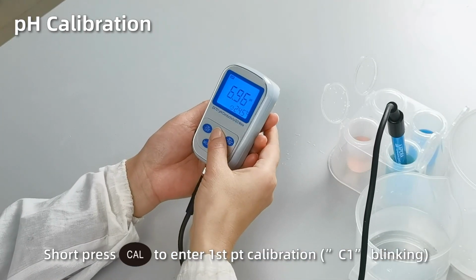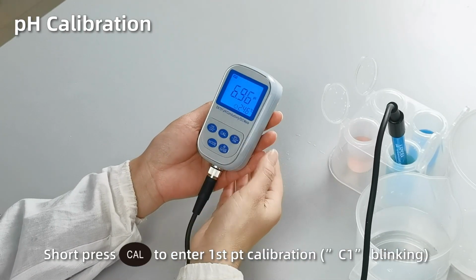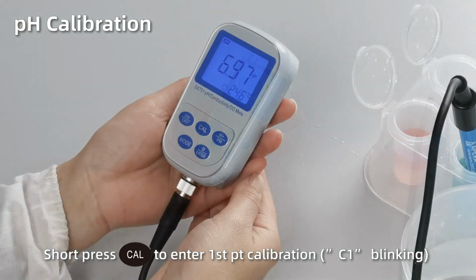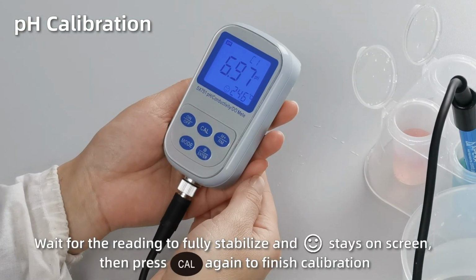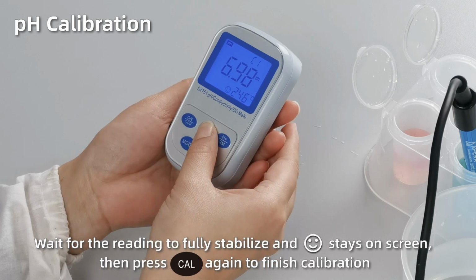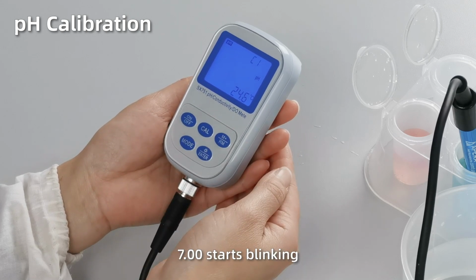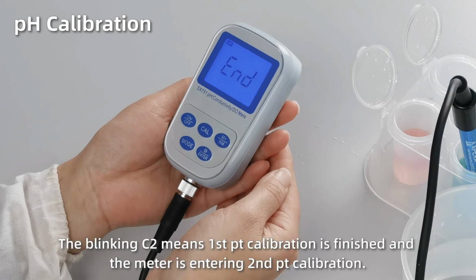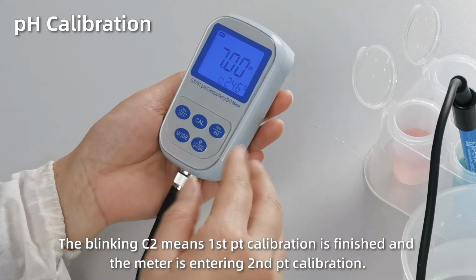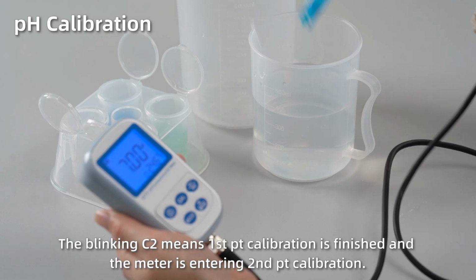Short press Cal to enter first point calibration, C1 blinking. When the reading gets fully stabilized and the smiley face stays on screen, press Cal button again to finish the first point calibration. 7.00 starts blinking. The blinking C2 means first point calibration is finished and the meter is entering second point calibration.